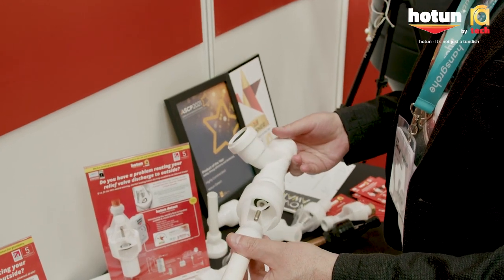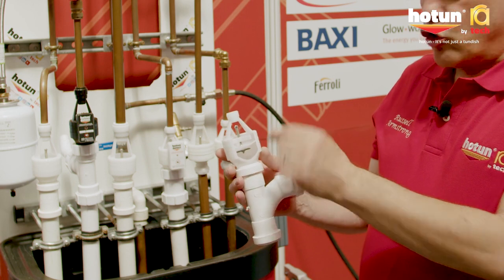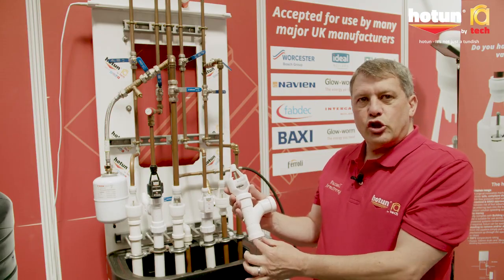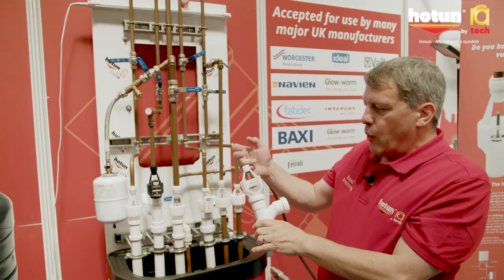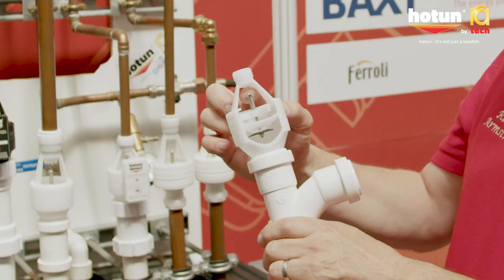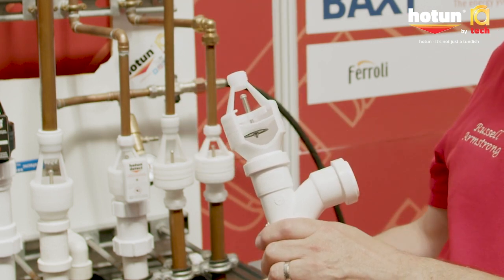The design of the Hotun dry trap Tundish is such that the spring rating is strong enough to keep the valve closed, so when we connect to a waste pipe you get no smells coming up from the waste pipe into the cupboard or the property. But when there's water dripping, the valve will open under the weight of the water and then close again once the water's flowed to drain.